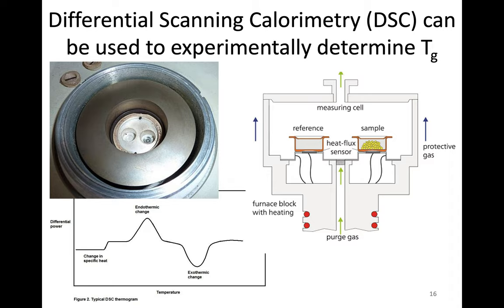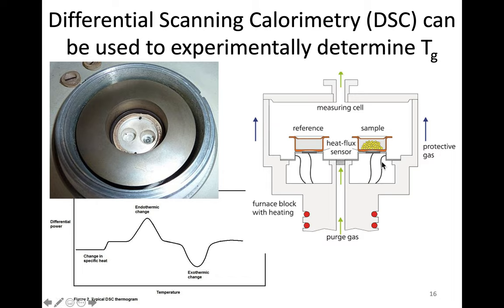DSC is used to experimentally determine Tg. The way it works is we have a furnace — in this case, actually two — and they're separated. We have one container known as the reference, where we keep either nothing or some material that mimics the sample. That's separated from the sample furnace, where we put the material of interest. Both are resistively heated — you can see the little wires underneath. This is all contained in an inert protective atmosphere, with purge and protective gas flowing through so things don't burn.